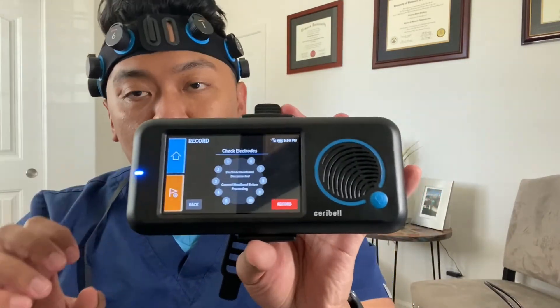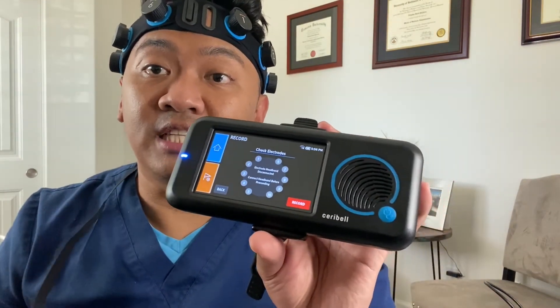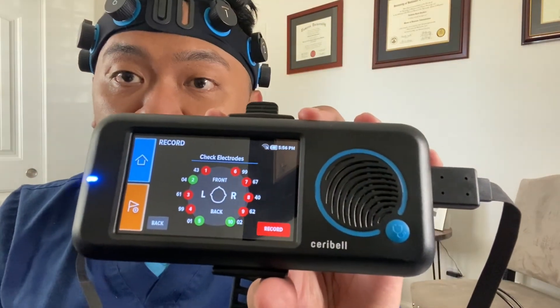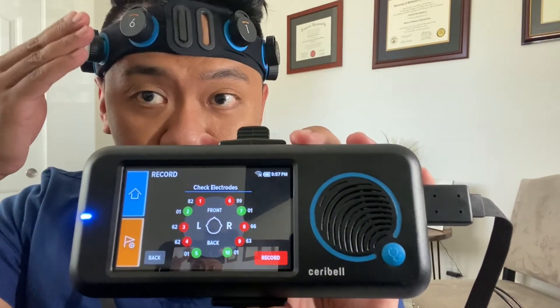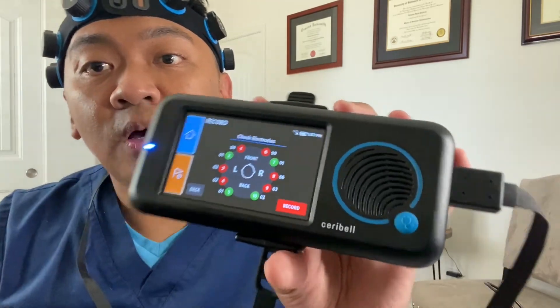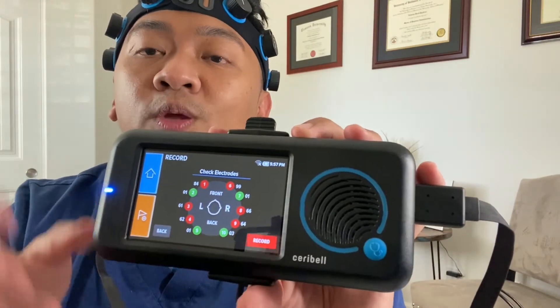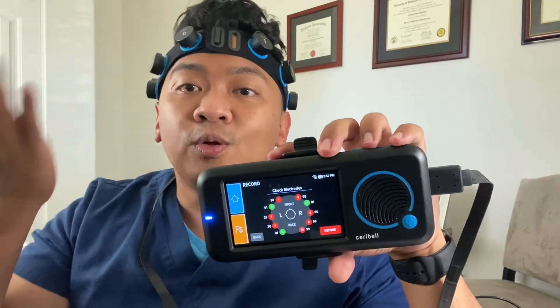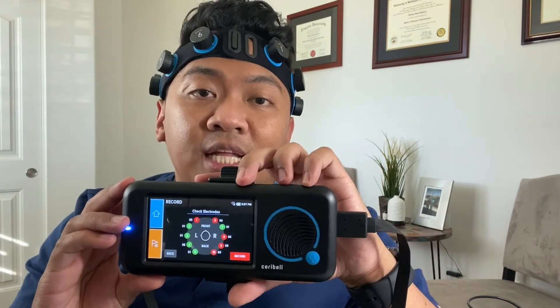After confirming, the electrodes will show up on screen. A gray electrode circle means the headband is not yet attached to the recorder. Once you attach it, you'll notice red and green indicators. You want to make sure all electrodes are green. Even if one or two are missing due to sutures or wounds, the machine can still read an EEG.